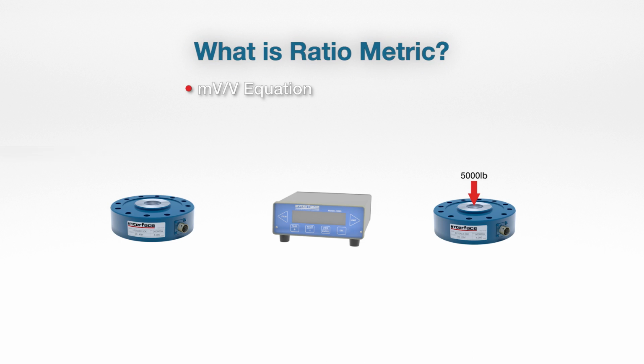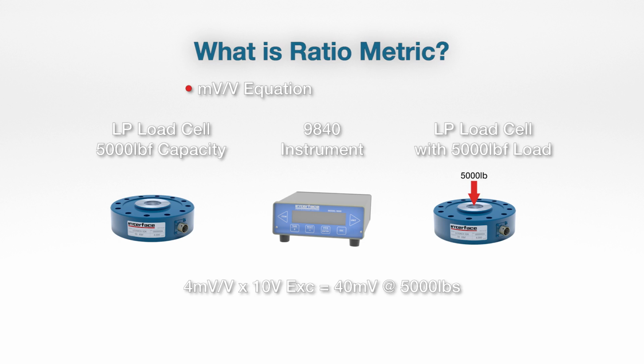All right, so in this example, we've got a 5,000-pound load cell connected to an instrument of some kind. In this case, this is our 9840. And then we have a load placed on the load cell. So again, we're going to assume a nominal output of 4 millivolts per volt, and assuming 10 volts of excitation, that means at full scale with 5,000 pounds on the load cell, you would see a nominal output of 40 millivolts. A variation of this would be if we only supplied 5 volts of excitation, we would expect half of the output, or 20 millivolts at 5,000 pounds.